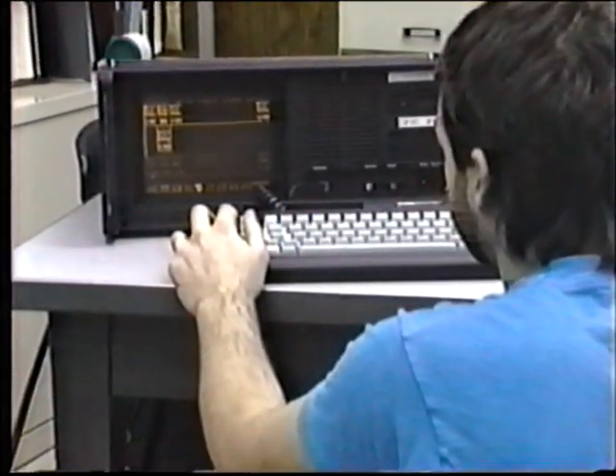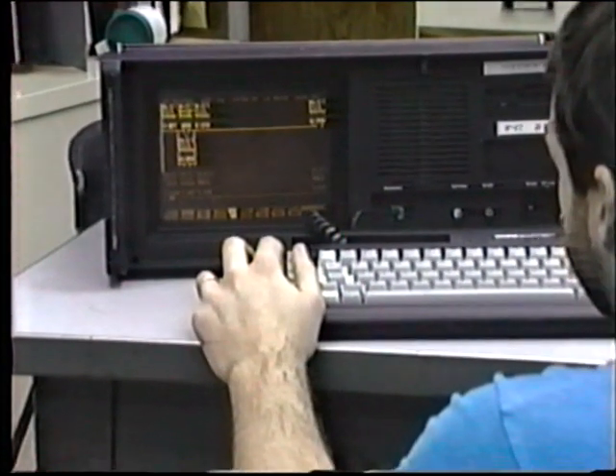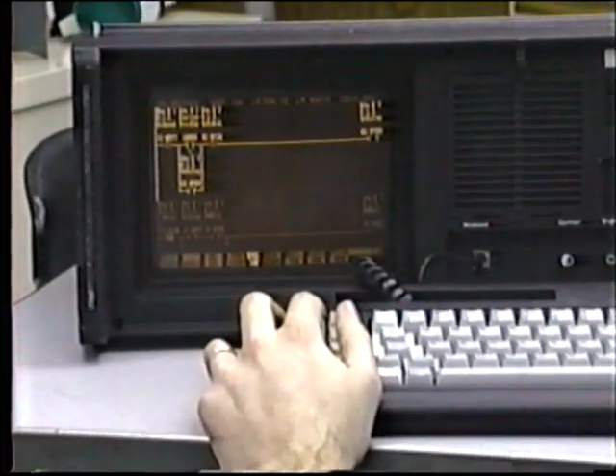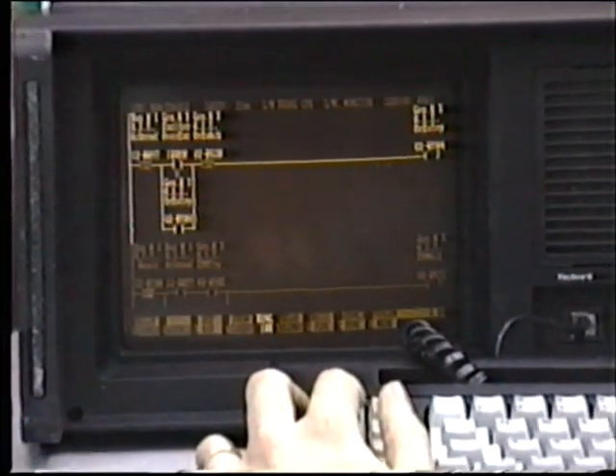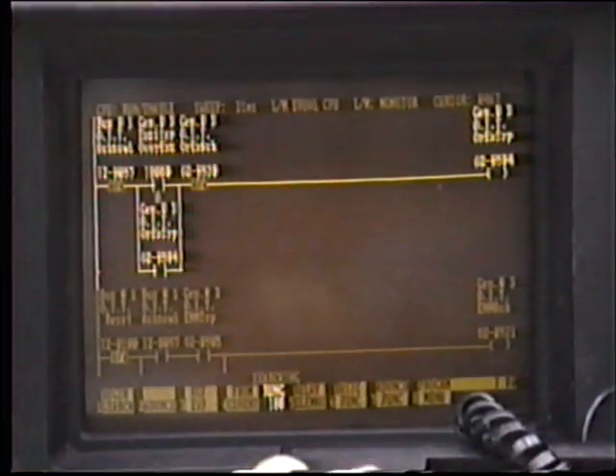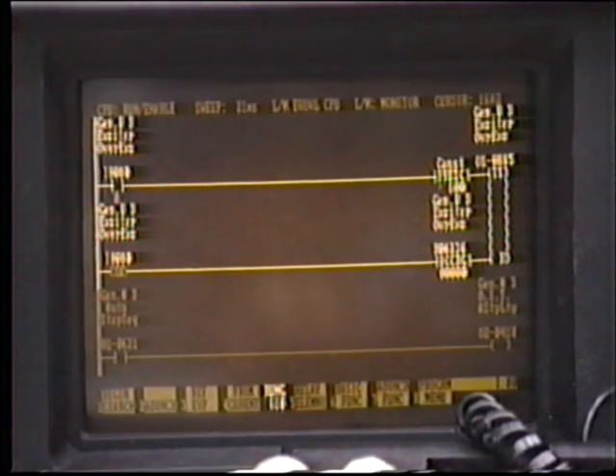Branch circuits can be drawn in and additional rungs added as required. Note that it is necessary to include an end rung at the completion of each sequence. Different coding methods are used by the different PLC manufacturers, although they may appear to be quite similar. Make sure that you practice and learn the program coding details for your own particular PLCs. Let's look at a few more examples of program logic.